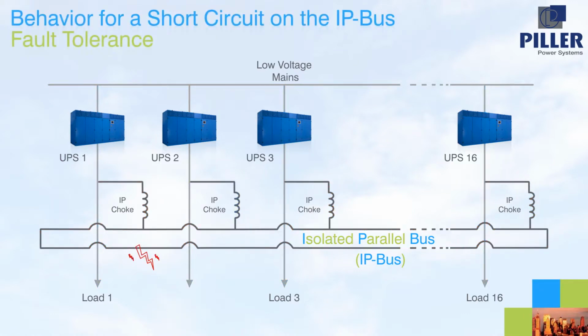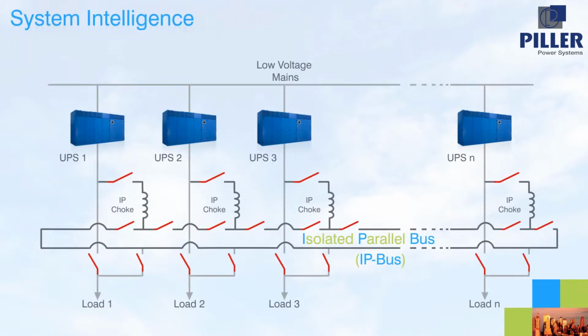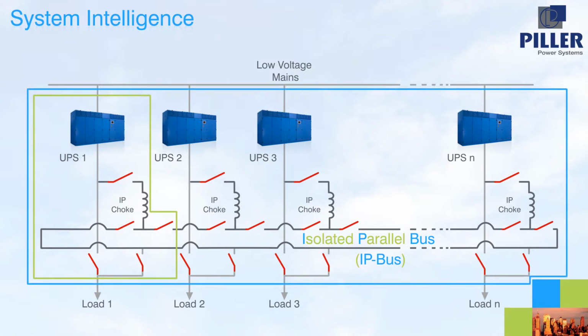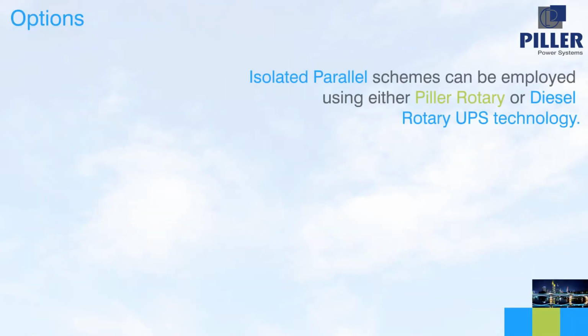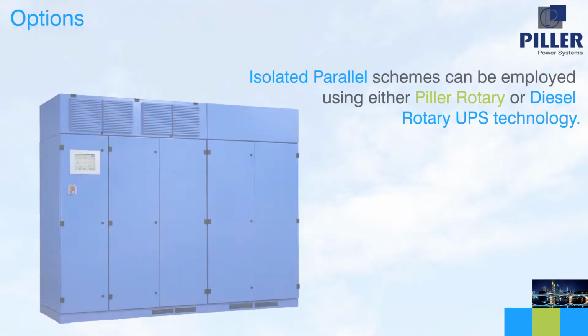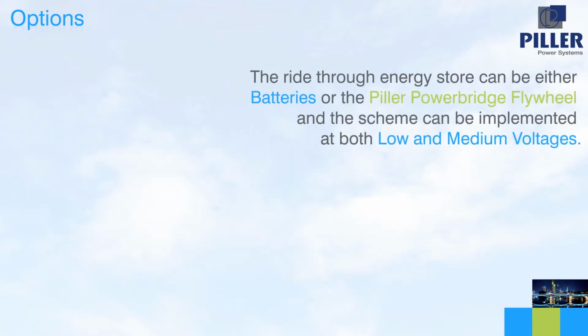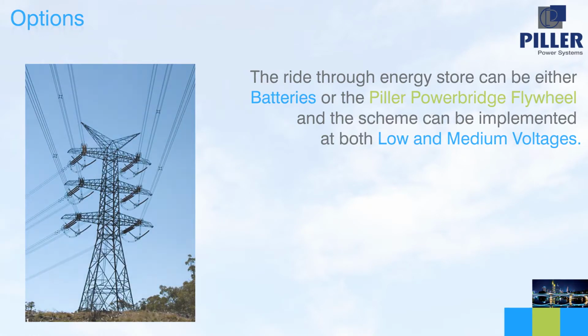A fault on the IP bus is also possible, although much less likely. Even in this case, where the currents can be higher, the fault is restricted to levels that fall within internationally acceptable limits for IT equipment. A simple control system is employed to provide all of the functionality, because much of the load and fault handling characteristics occur naturally. A collective control for all systems is not essential, but can be added to optimize functionality. Isolated parallel schemes can be employed using either Piller Rotary or diesel rotary UPS technology. The ride-through energy store can be either batteries or the Piller Powerbridge Flywheel, and the scheme can be implemented at both low and medium voltages.